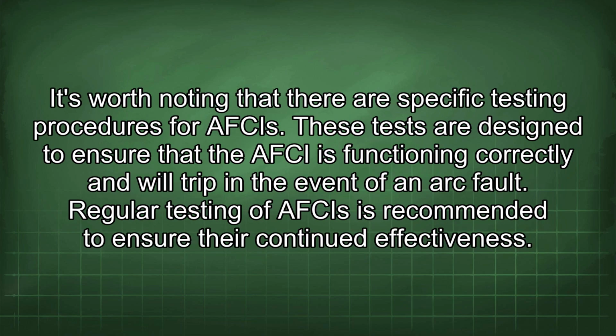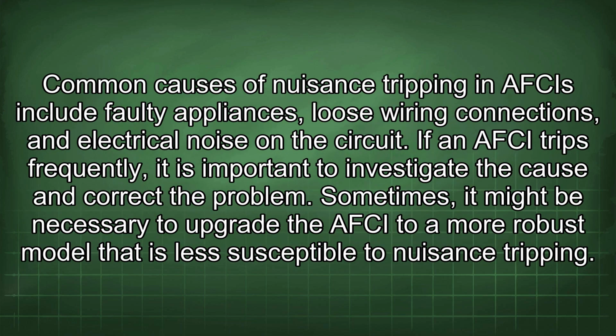It's worth noting that there are specific testing procedures for AFCIs. These tests are designed to ensure that the AFCI is functioning correctly and will trip in the event of an arc fault. Regular testing of AFCIs is recommended to ensure their continued effectiveness. Common causes of nuisance tripping in AFCIs include faulty appliances, loose wiring connections, and electrical noise on the circuit. If an AFCI trips frequently, it is important to investigate the cause and correct the problem.